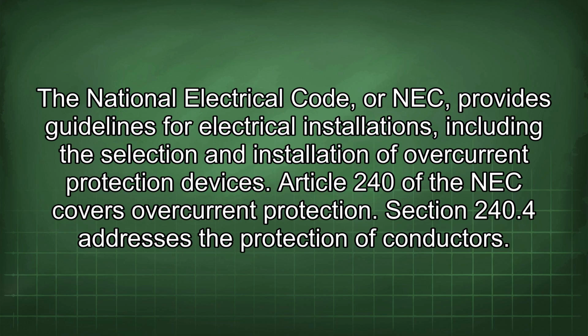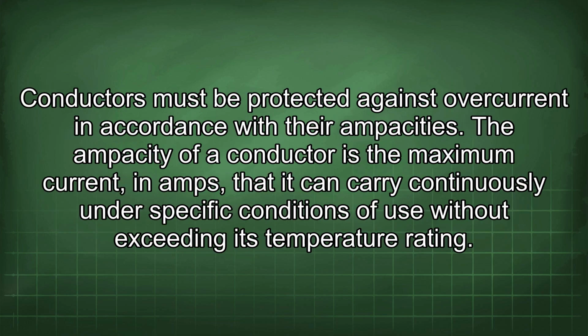Article 240 of the NEC covers overcurrent protection. Section 240.4 addresses the protection of conductors. Conductors must be protected against overcurrent in accordance with their ampacities. The ampacity of a conductor is the maximum current in amps that it can carry continuously under specific conditions of use without exceeding its temperature rating.